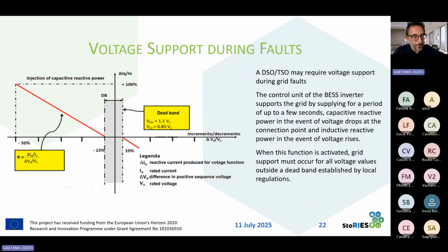And this is a future step in the service that storage systems can provide to the grid, because here we have another important function that must be implemented by storage systems during the fault. So it's important not only that the storage system stays connected to the grid during the fault or during the transient that will occur later, but in some cases the same storage system must help the grid, supporting the voltage in the point where it is connected.